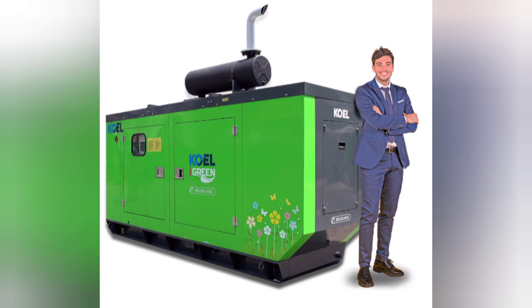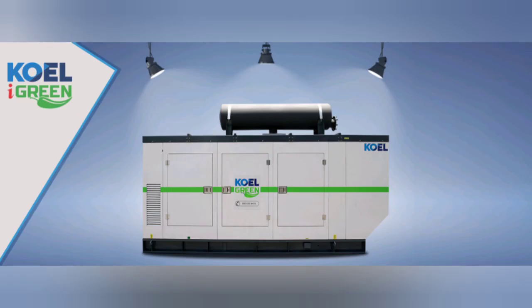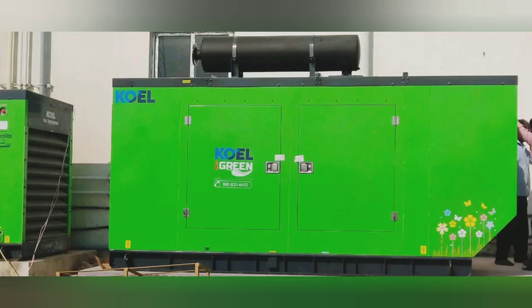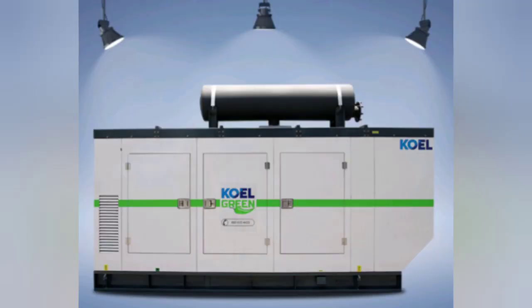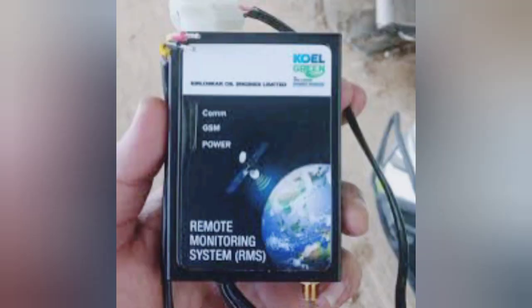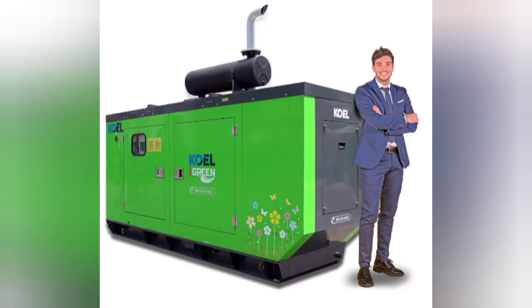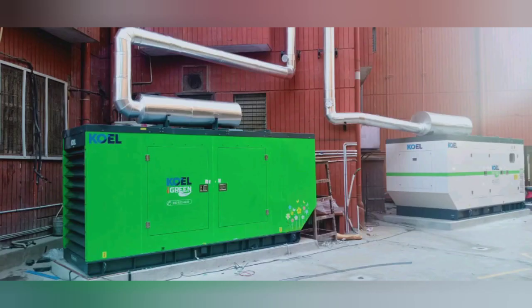Here we are fixing KRM in 160 kVA and 200 kVA KOEL Green gensets. As you all know, the 160 kVA genset comes with the KG645 controller and the 200 kVA genset comes with the KG745 controller. Though both the devices look similar, the communication ports are different. First, let us see how to fix KRM in the 160 kVA genset, which has the KG645 controller.